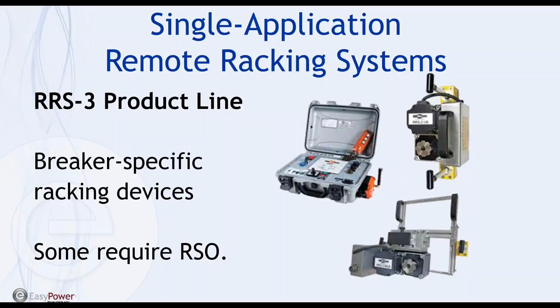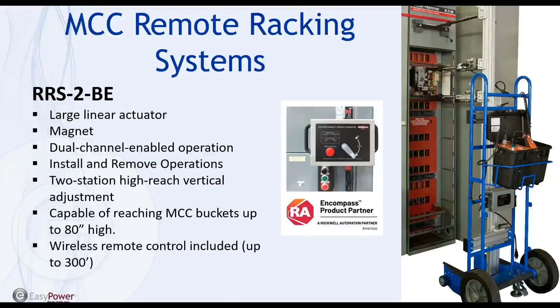We also now offer MCC remote racking systems. Similar to the cart the RRS1 was designed on, we have what's called the Remote Racking System 2 BE, which stands for bucket extractor. This device pushes or pulls MCC buckets in and out of their cubicles. There are alignment features: a magnet system on the top of the switchgear lineup, and again on the bottom, an attachment for any type of extraction-style MCC bucket, and this device racks it for you. It gives people a lot of comfort to be able to do that. It's capable of reaching up to 80 inches high, with extended slides to help it get as high as you need to go. It also offers a wireless remote system that can get up to 300 feet away.